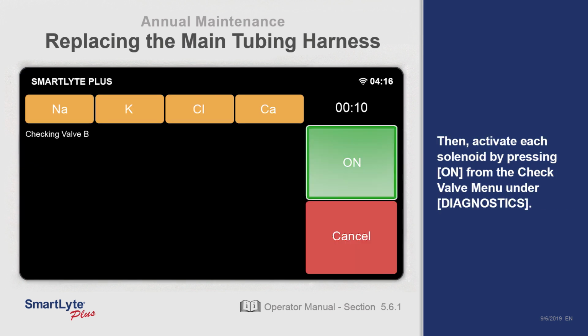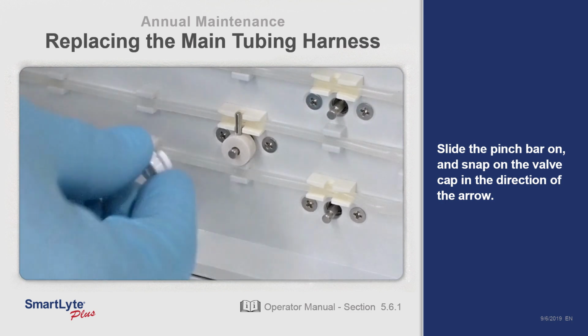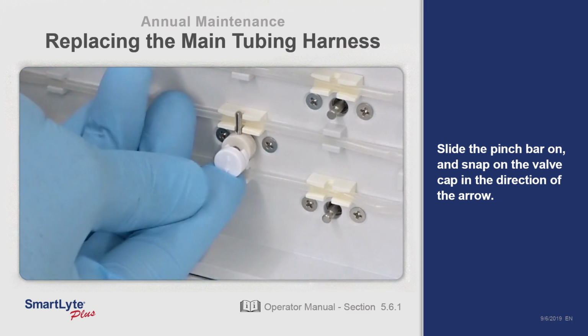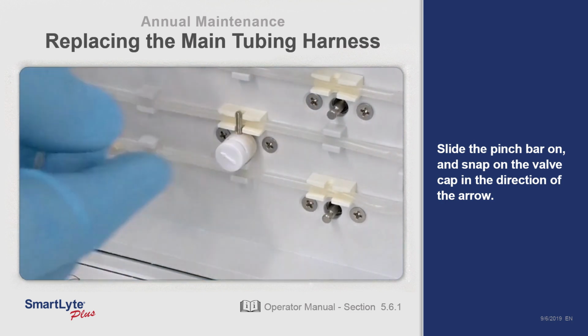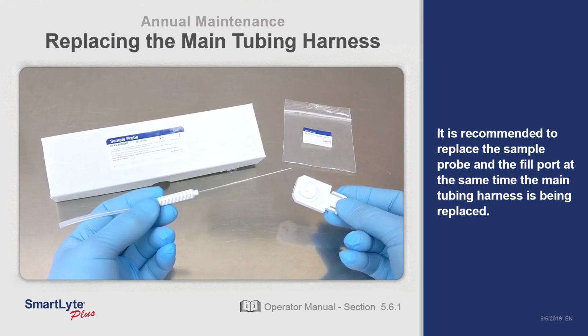Then, activate each solenoid by pressing on from the Check Valve menu in Diagnostics. Slide the pinch bar on and snap on the valve cap in the direction of the arrow. It is recommended to replace the sample probe and fill port at the same time the main tubing harness is being replaced.